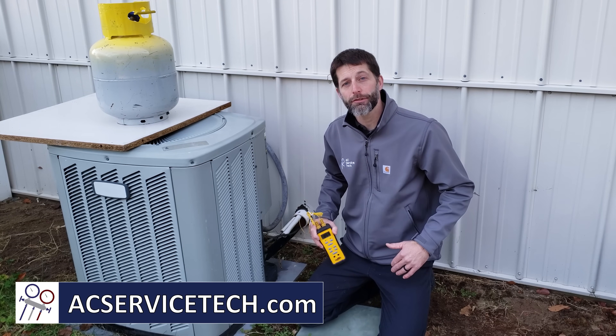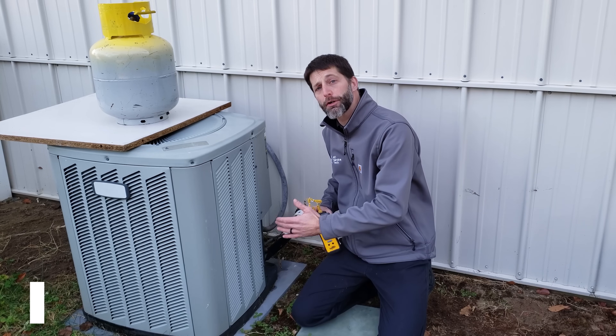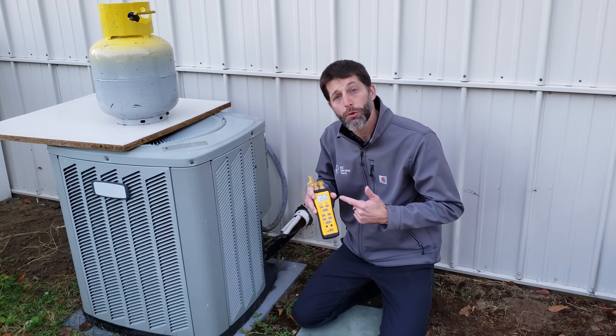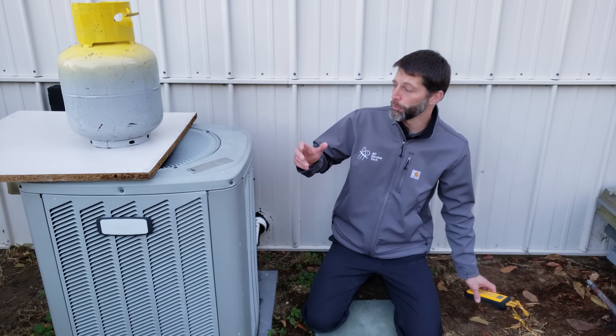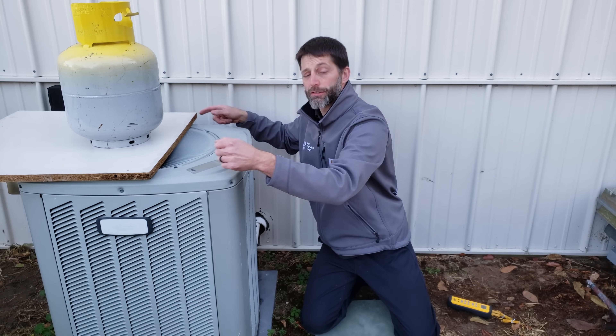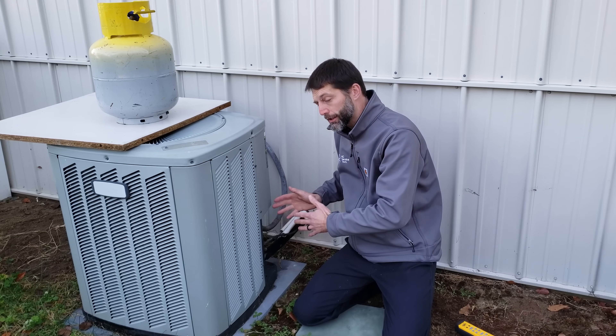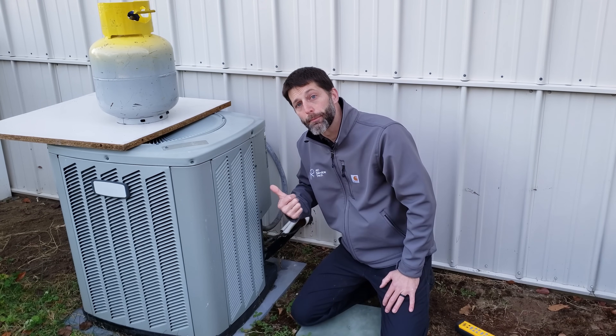This is Craig Migliaccio from AC Service Tech, and today we're going over how to check the refrigerant charge on an air conditioner or heat pump during low outdoor ambient temperatures. We can replicate a higher temperature day by restricting the airflow on the top of the unit in order to drive up the pressure to correctly check the refrigerant charge.